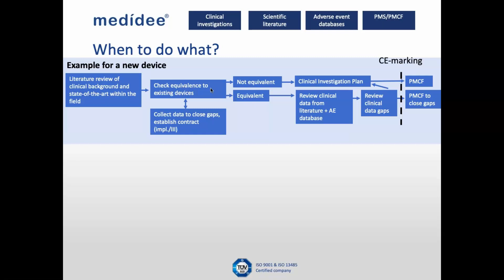Another example here is from an existing device which is CE marked and is based on equivalent devices under the Medical Device Directive. And this is a case that we have encountered multiple times. If you have such a device on the market, you need to very thoroughly review if the equivalent device is still valid under MDR. So you need to go through all those clinical, biological, and technical characteristics and check for each of those if they can be considered to be similar to the extent that there is no clinically significant difference in performance and safety. And remember that you need to have data to substantiate that these devices are not too different for that to be claimed.